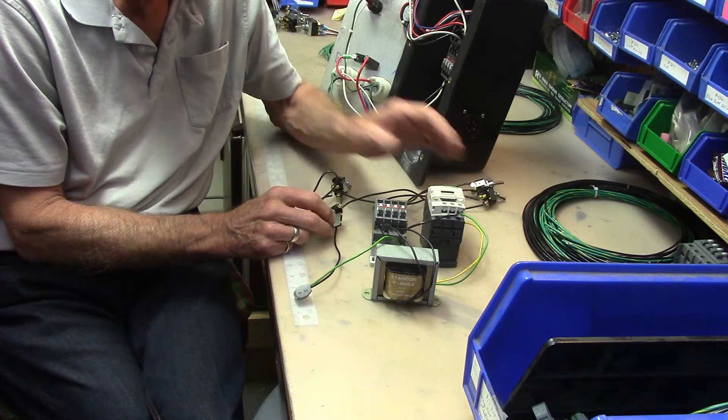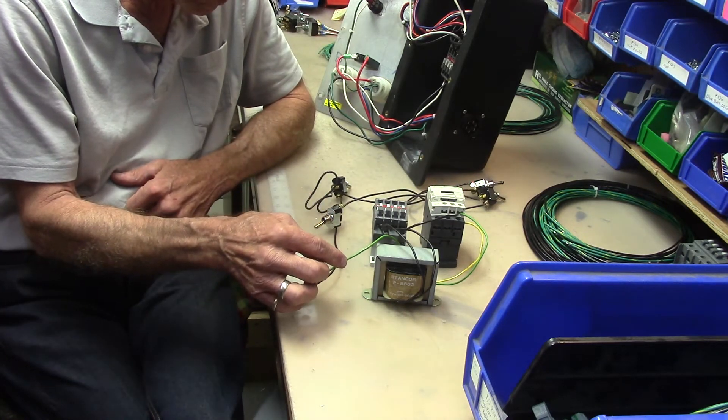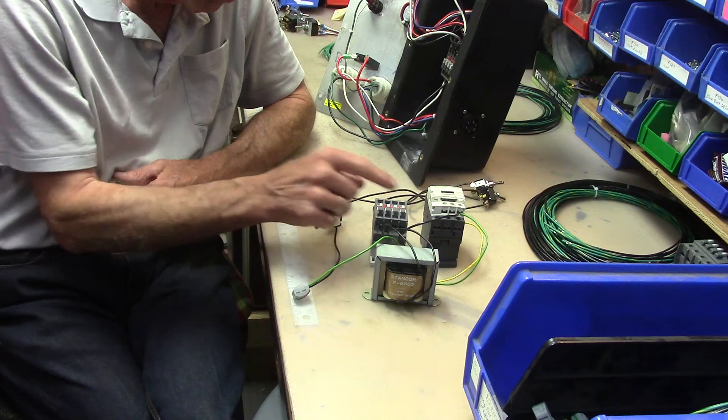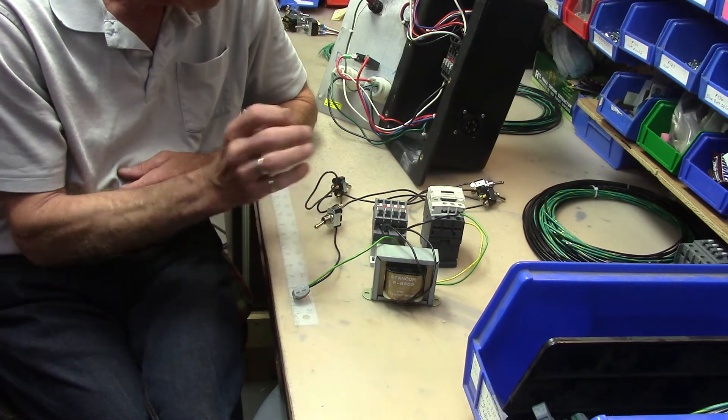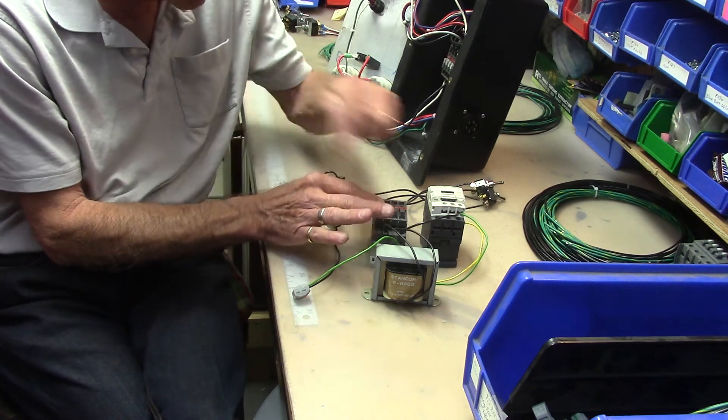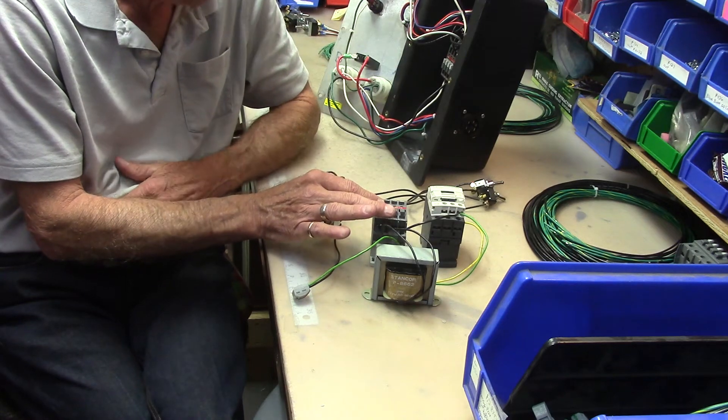The ultimate test for a contactor would be to put 24 volts from both wires to the contactor directly and see does it pull in. If it pulls in good and solid and has a good ohms check across, it's good.